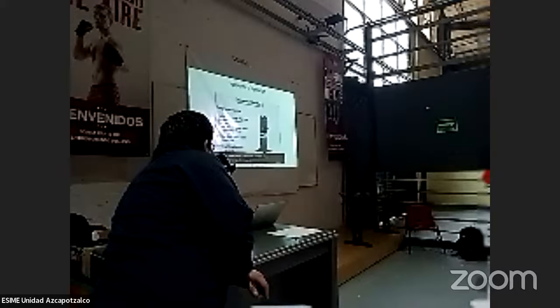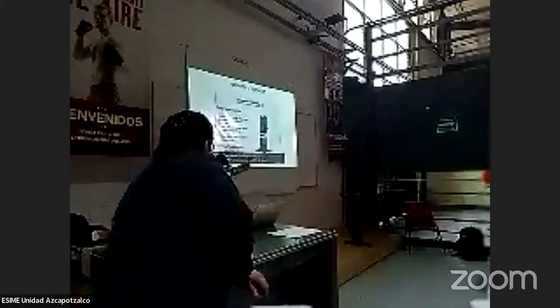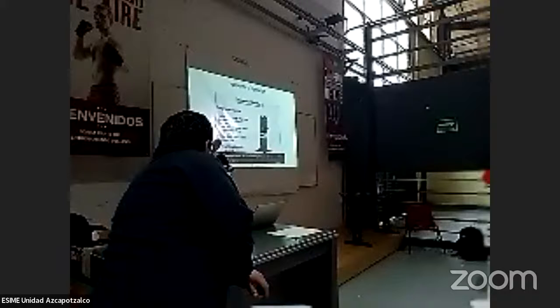And if you're in overdrive, let's say for some reason where I'm from, and definitely where David's from, it can get above 100 and stay above 100. Well, on those days, if it's 105 outside, then that compressor could be in overdrive. If it's in overdrive, it's going to be screaming. It's going to make that loud, whining pitch noise. And so that may make your customers think that there's something wrong with the unit, and there's not. So that's the reason I mentioned this. If you hear that high pitch whine, verify the RPM before you condemn the compressor.